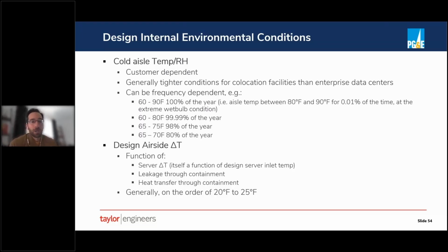So what are the appropriate conditions for cold aisles? They're highly customer dependent. What we generally find is that colocation facilities want tighter environmental conditions than enterprise data centers. And this is simply because they have multiple customers within the data center and they're trying to cater to the needs of the most conservative customer in many cases. That in turn drives them to using more conservative conditions broadly across the data center, because it's not like you can have a server cage in one part of the data center that, particularly for using something like an underfloor distribution, that's controlled to one set of conditions, and another part of the data center in that same data hall that's controlled to a different set of conditions.